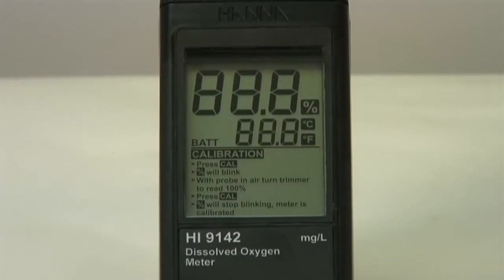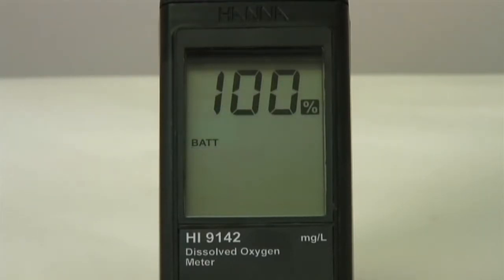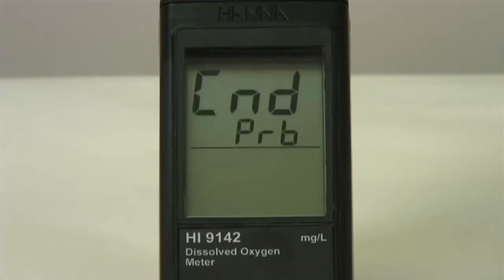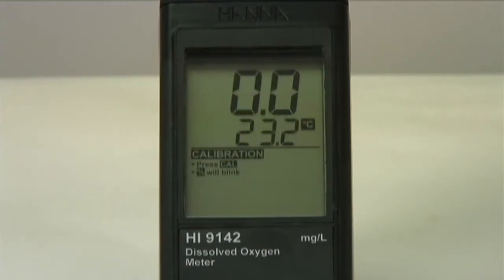Once you've inspected and set up the HI9142, go ahead and turn on the meter. The LCD display will show all of its segments and then indicate the battery life. The conditioning probe message will then appear. This means the probe is polarizing. It takes a few minutes, but polarization is essential for stable and accurate readings. Once the message disappears, the probe is polarized, and the meter is ready for internal setup and calibration.